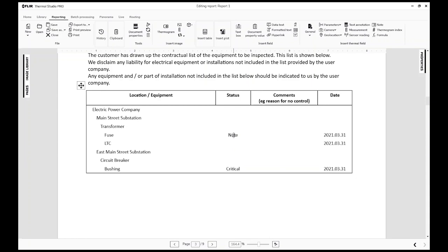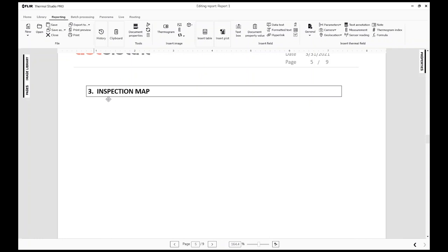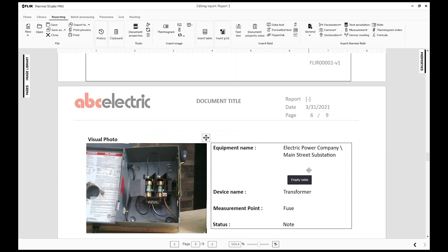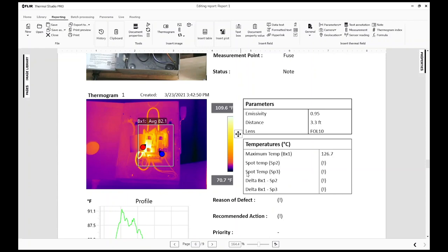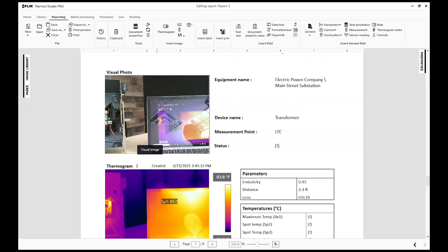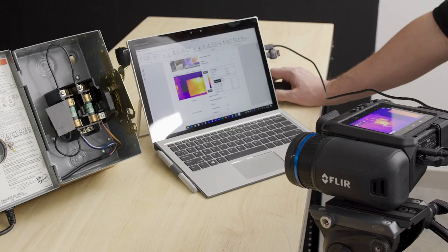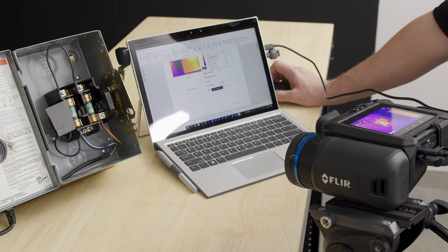We now have a full report. It includes a table of contents and a summary of equipment — the fuse, the LTC, and the bushing — with their statuses such as Note and Critical. If GPS was enabled, a map showing the location would appear here as well. Each finding page shows the visible and thermal images, the area box measurement, camera settings, and lens information. You can still double-click to move measurement spots, then hit Print to send the report off to colleagues for further inspection.